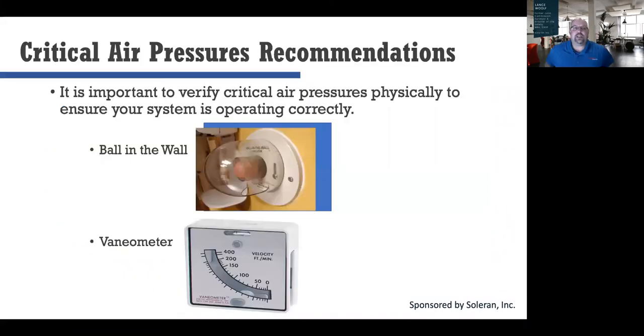So here's some recommendations for your critical air pressures, and this is what I recommend for your survey. It's important to verify your critical air pressures physically and make sure your system is operating correctly, because I've had examples on survey where the dashboard was giving false readings.